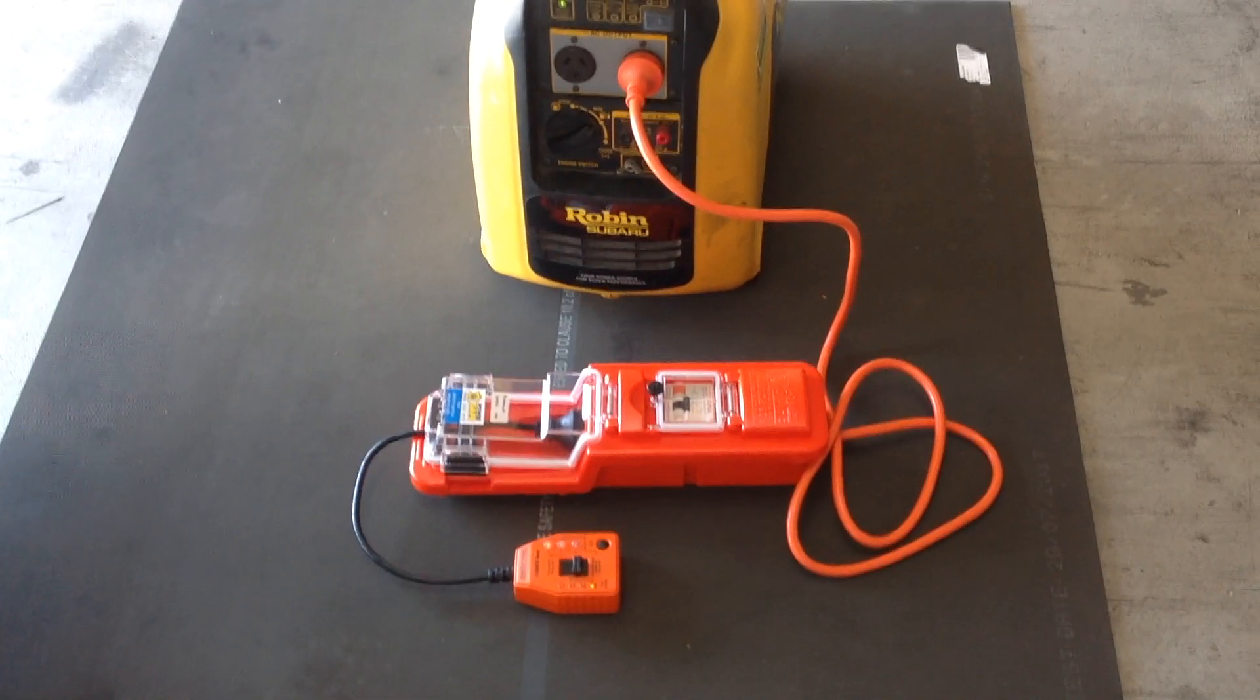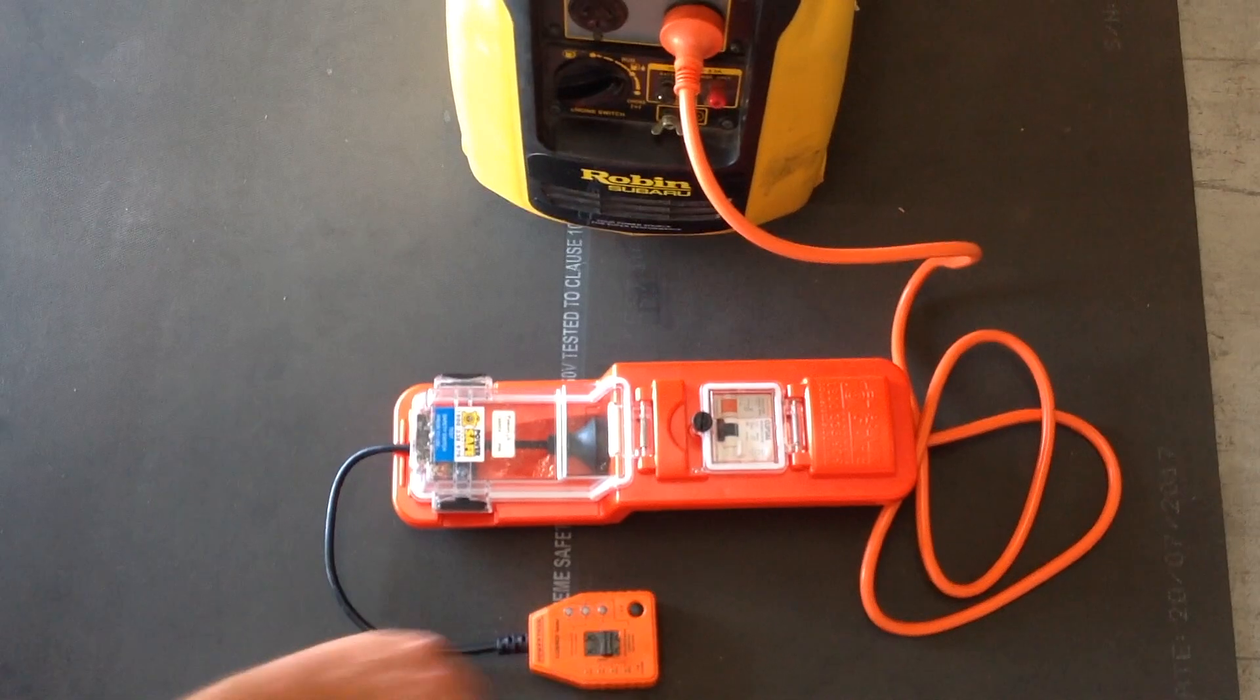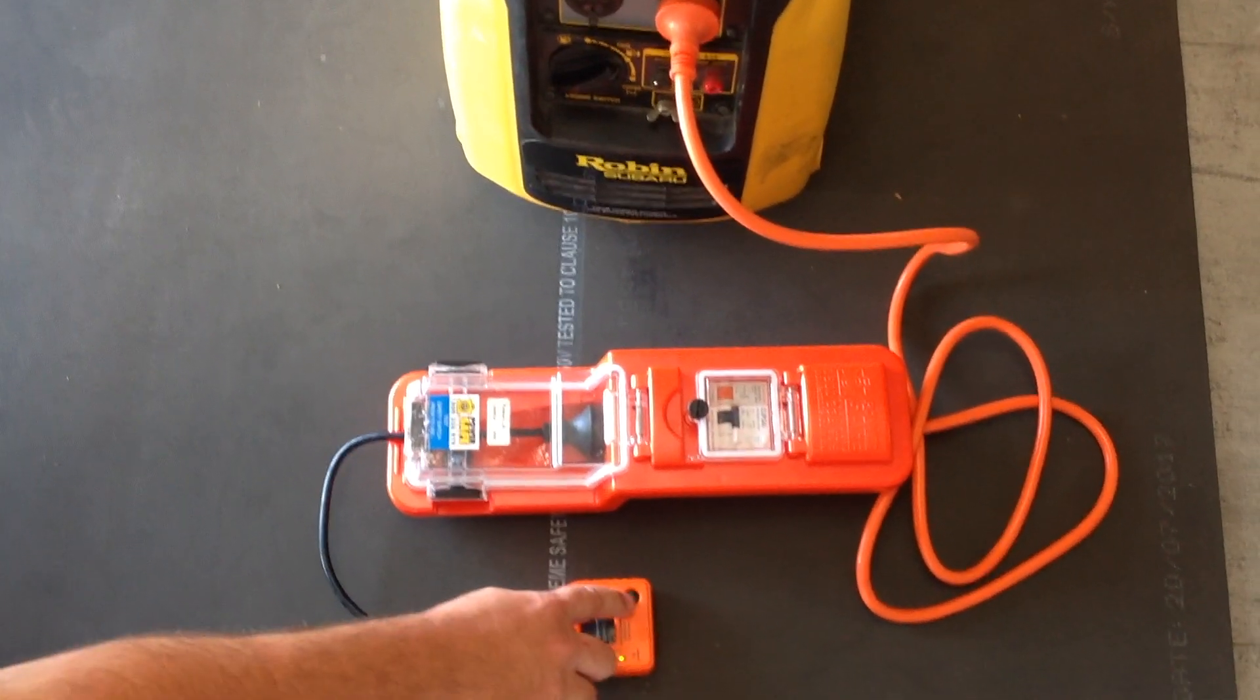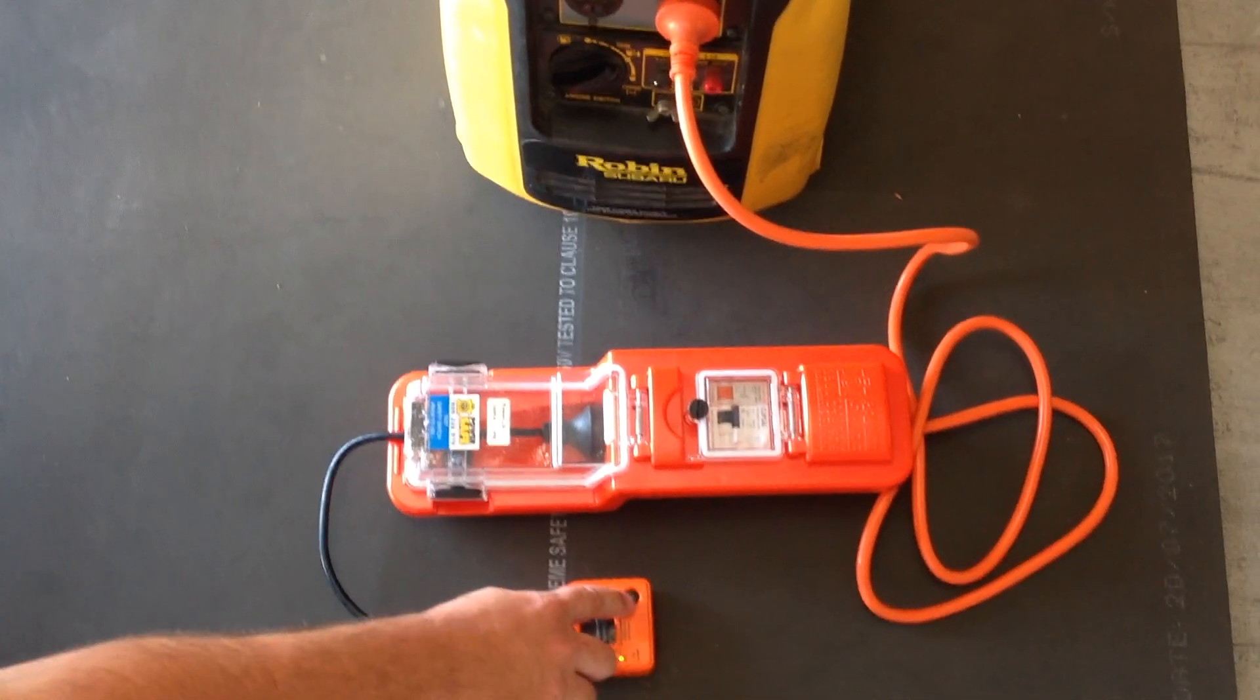so in the event that a first fault occurs, then the ESD part of the DUO will trip the device as it is measuring voltage on the earth circuit, and see that the earth circuit has potential voltage greater than 38 volts.